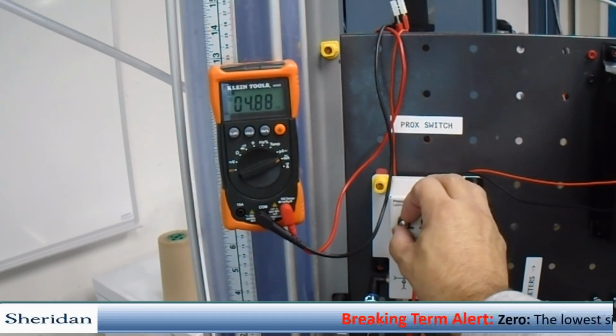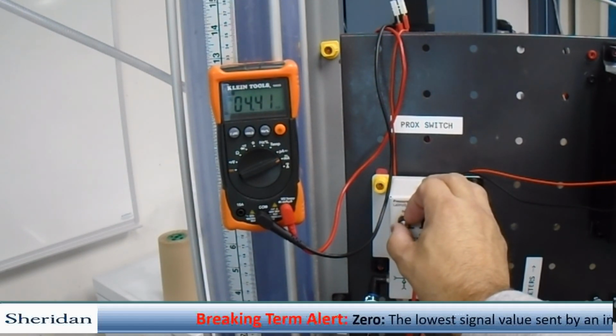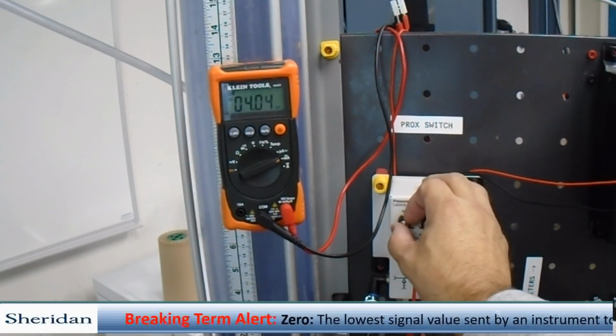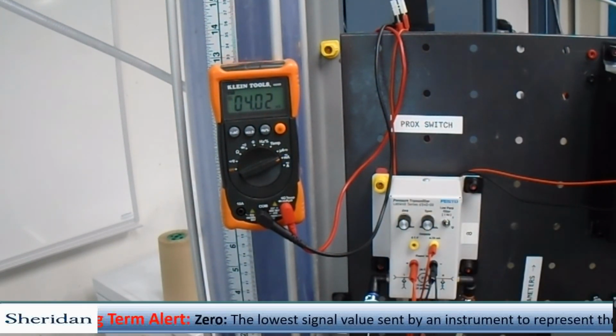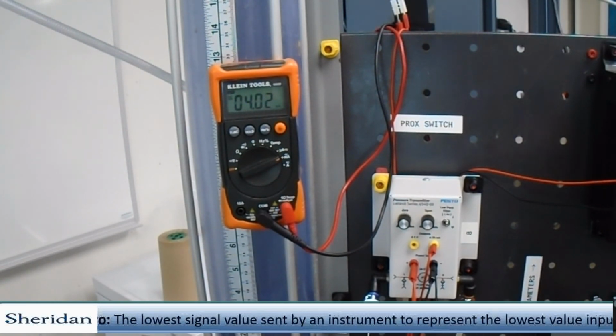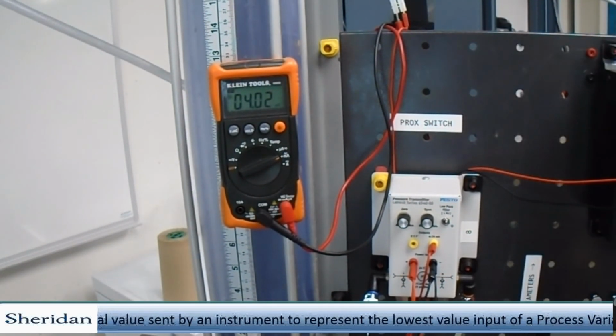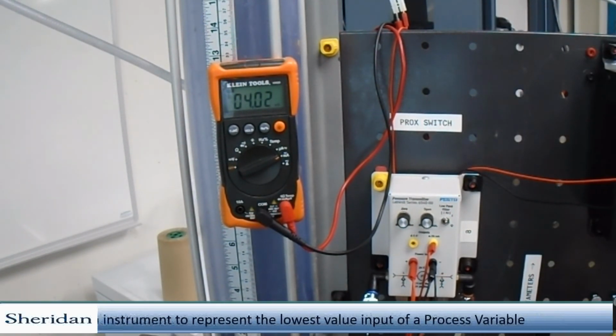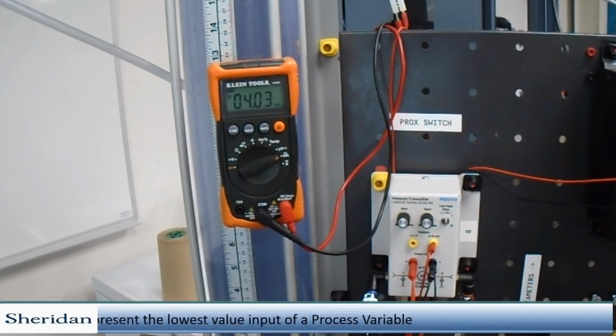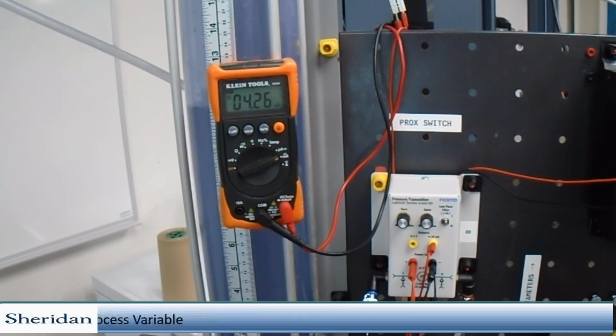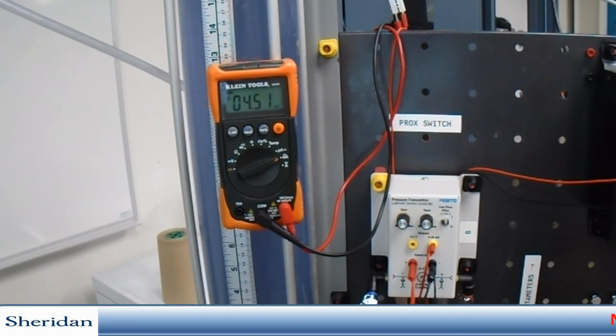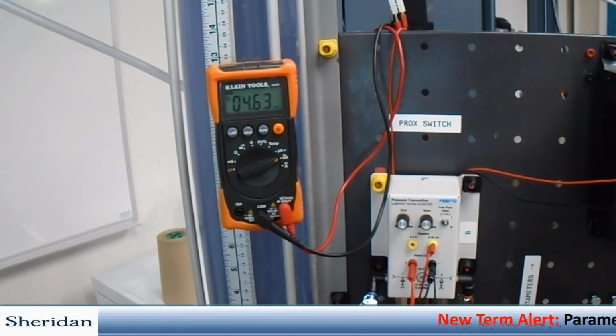So I'm now at 5, so I'm just going to move it just slightly, let it stabilize. So I'm at 4.02 milliamps, so I'm going to leave it there for now, and now I'm going to add more water and bring it up to our upper level. So once I reach 20 inches, I'm going to stop the pump. Let it come back down to 20 and stop it by closing the valves.